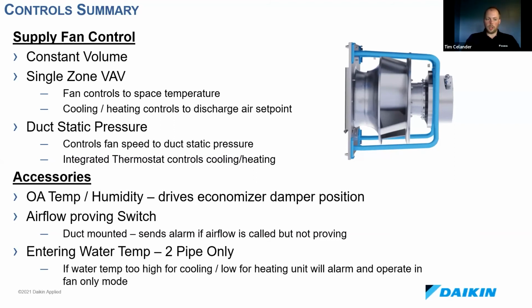It won't shut down the unit though. And then I guess kind of the last accessory I want to touch on is an entering water temperature sensor. In your market, if you're not doing reheat and you have a 2-pipe chilled water hot water coil, you're going to have a temperature probe upstream of that, measuring that water temperature. So if you get a demand for heating in the room, but you have chilled water going to the unit, it's going to operate in fan only mode rather than dumping or performing cooling when you're asking for heating. And obviously the opposite is true as well. So if you're asking for cooling, you have hot water.